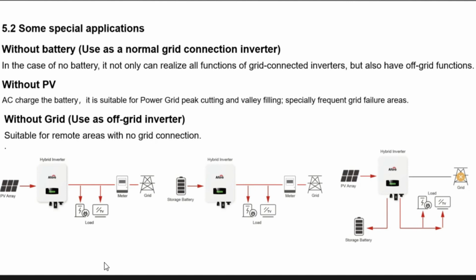Yes. That's a big function. A lot of suppliers don't have that function, island mode. Yeah, but like I said, it won't put any power back down the AC. Yeah, because there isn't an AC, but it will put power out on the essential circuit supply. But you do need to be a little bit careful when calculating the maximum output of the inverter against the load you put onto the system.